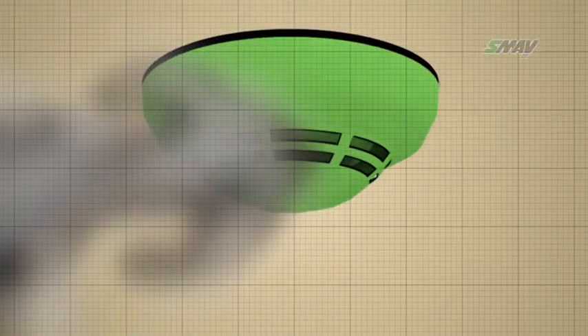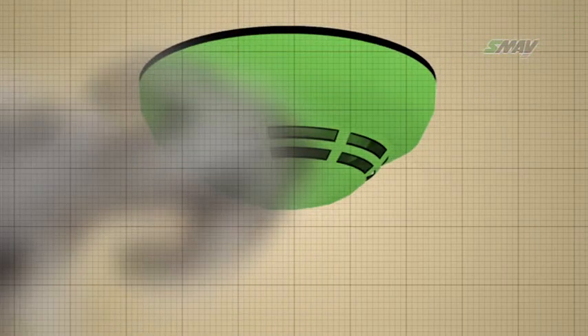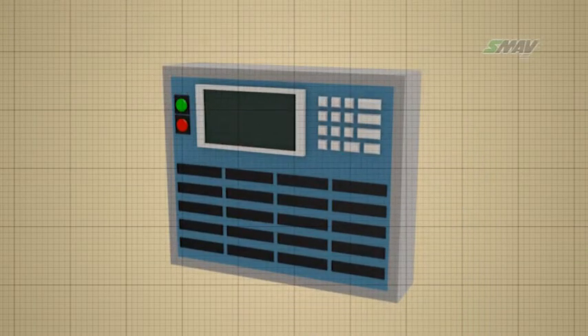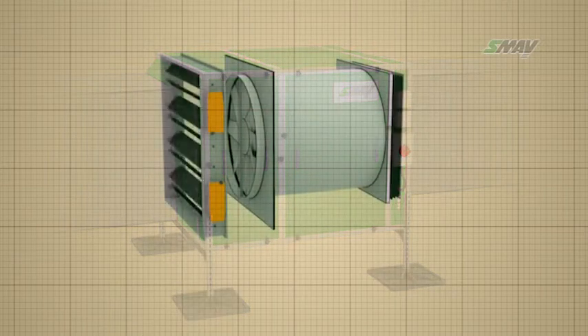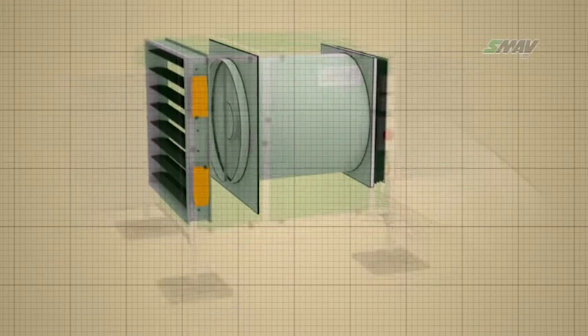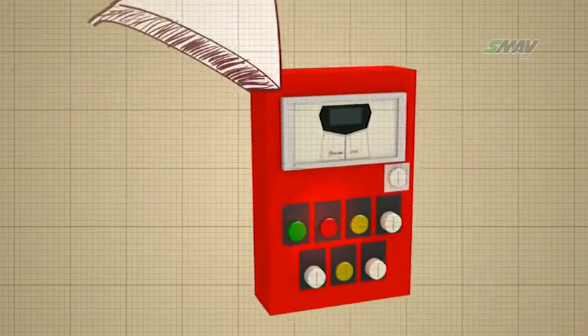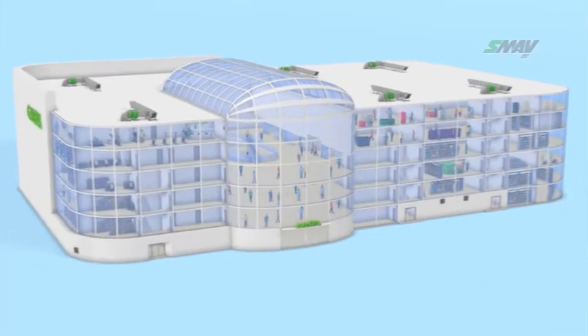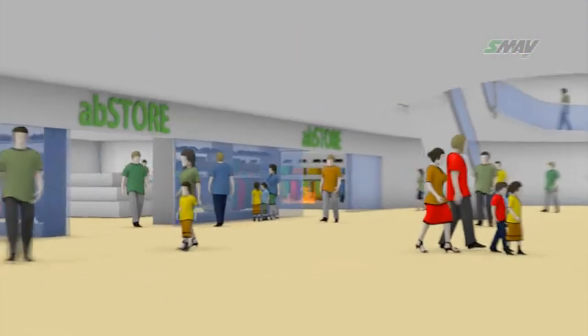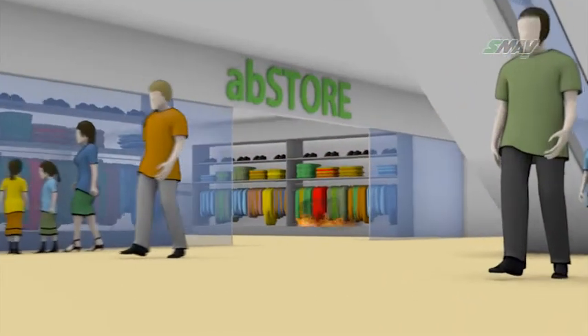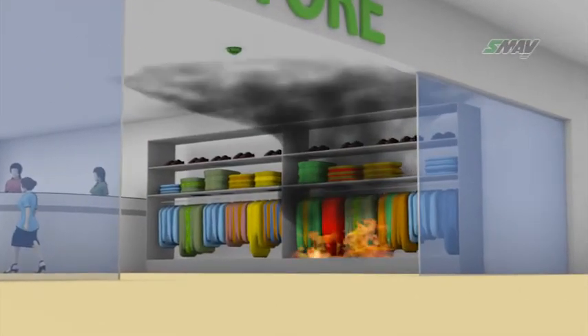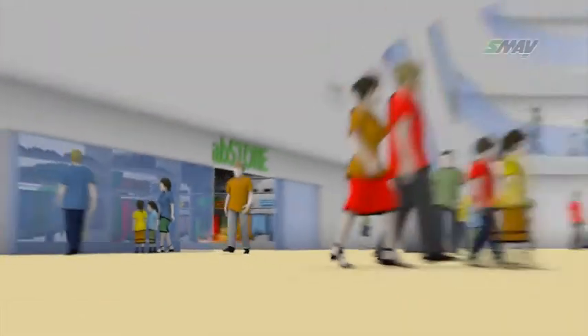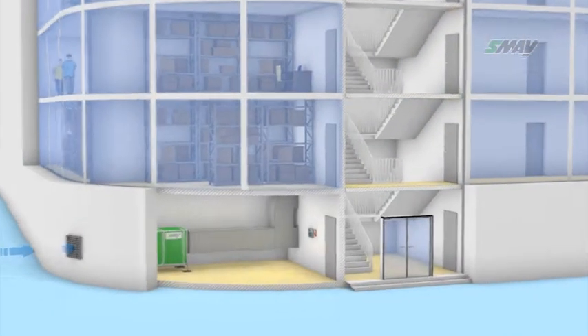When fire breaks out and smoke activates smoke sensors, this information is transmitted to fire alarm control and indicating equipment which switches iSway unit on. Information about switching on iSway unit is then transmitted to TSS board. If there is a fire in the building, the pressure differential system will be activated, producing said value of the overpressure inside the staircase, for example 50 pascals.